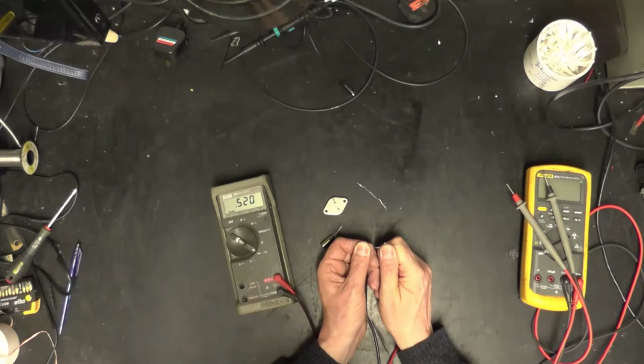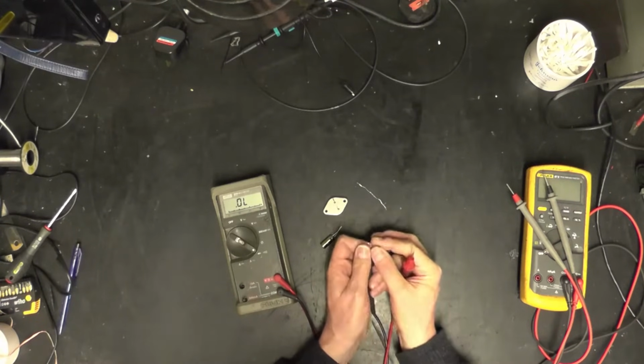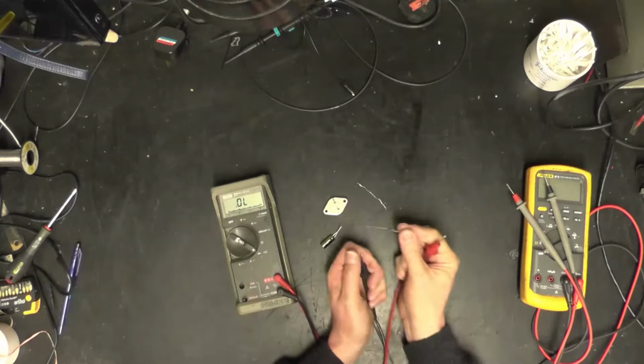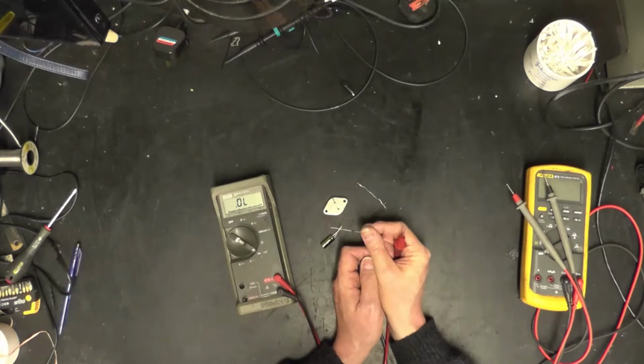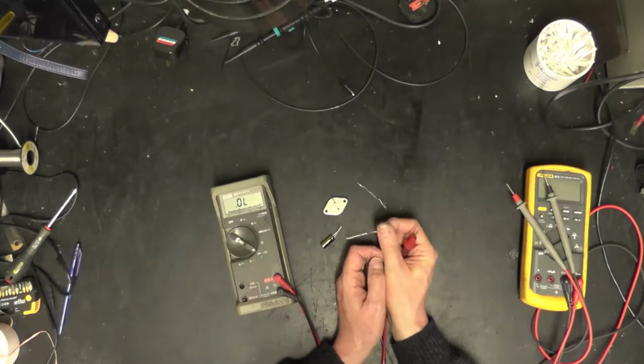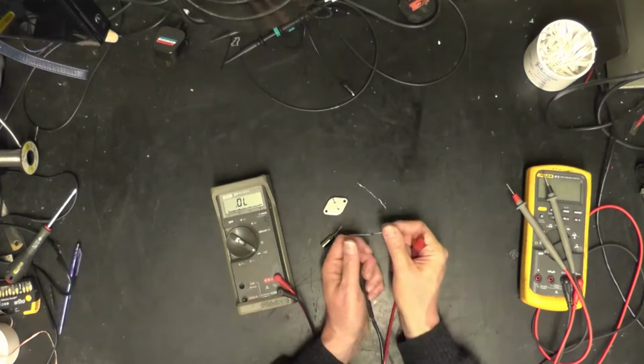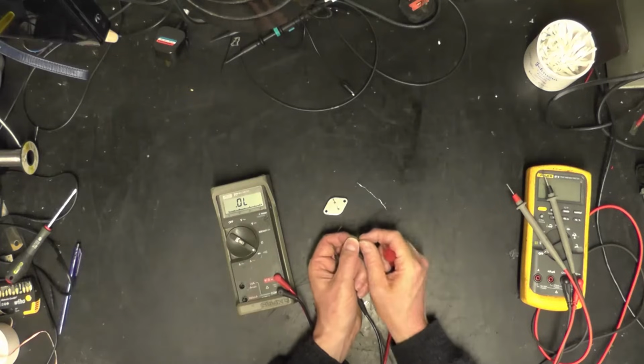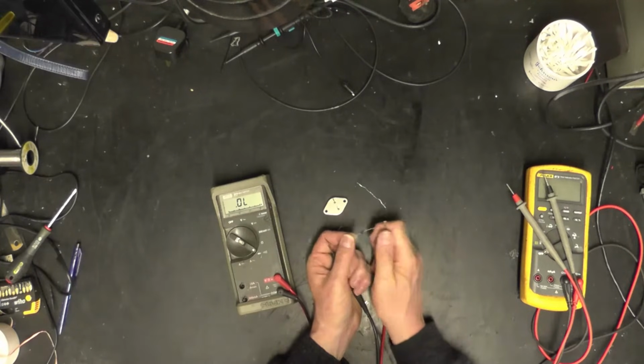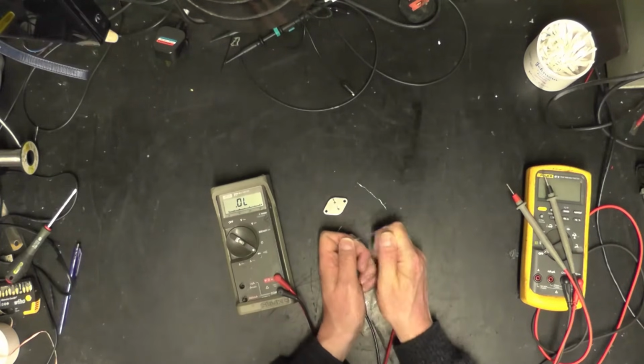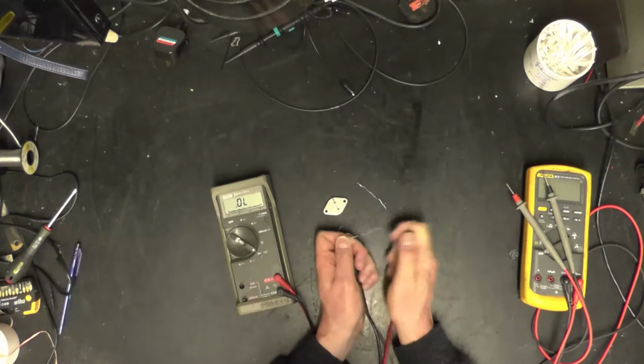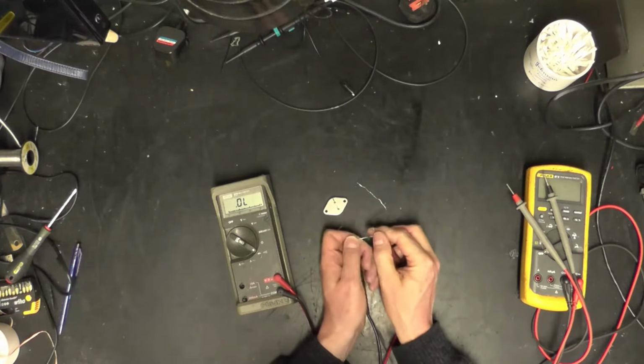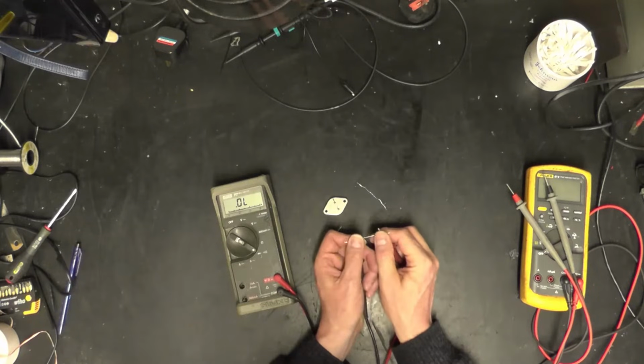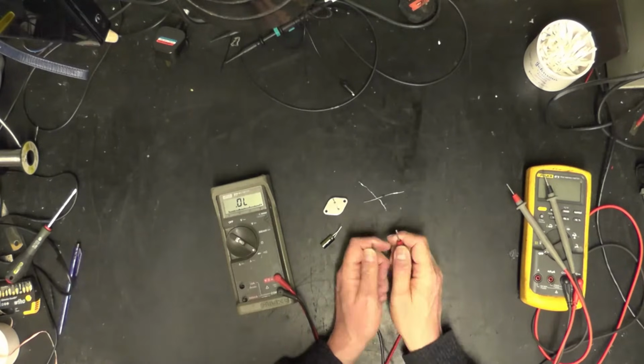There it is. One way and the other way, it's open. If you've got a diode that measures open circuit in both directions, it's a good chance it's no good anymore. And if it's short circuit in both directions, it's had it. Those are the sort of two methods of failure. You can get leaky diodes. And then you may get a reading in that reverse direction where you'd normally see open, you may get some leakage reading. But this is a good basic test.